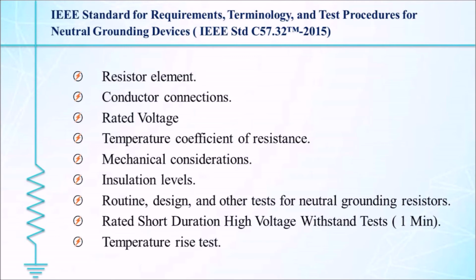One NGR is often used to limit the ground current on several outgoing feeders. This reduces equipment damage, limits voltage rise and improves voltage regulation. Since ground faults could occur in rapid succession on different feeders, a 10-second rating is not satisfactory. The 1 minute rating is applied. The rated time temperature rise of 60 seconds shall be taken as the sum of the steady state rise and the additional rise caused by the flow of rated current for the rated time temperature rise test.